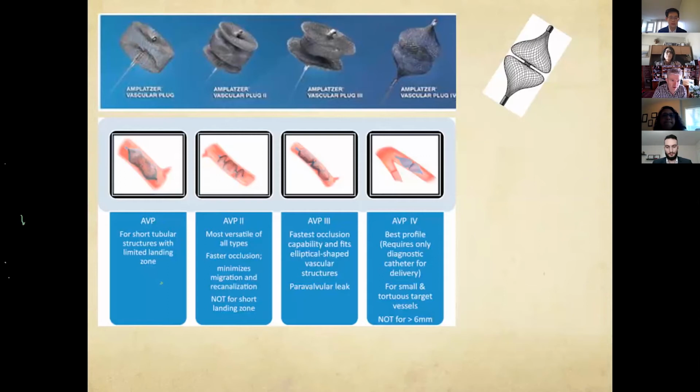So one of our very favored devices is called a vascular occlusion plug. And it's a very nice device. Very well designed, and it comes on the end of a wire. What you do is you put it in a thin tube that's all the way to where you want to deliver it. And then you push it gently out through the end of the tube, and it pops open, coming out of its constrained state and popping open to a bigger size.